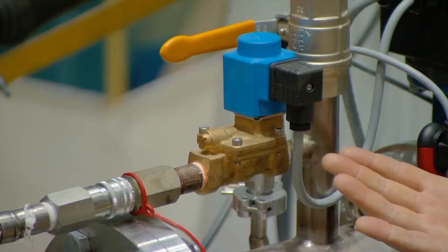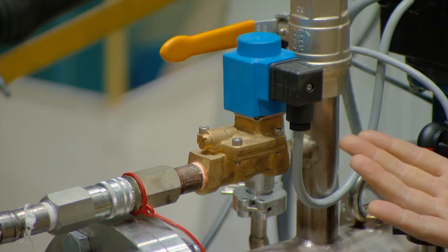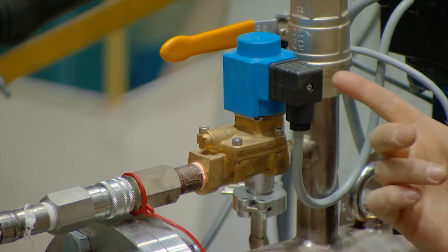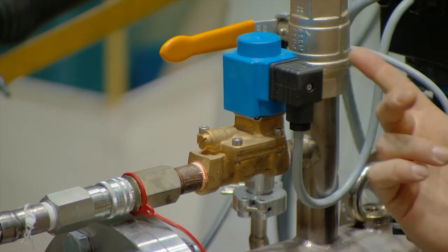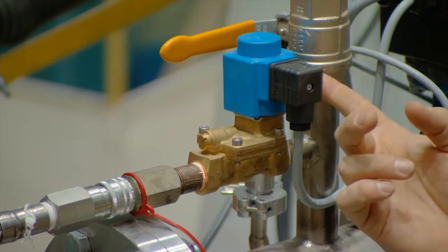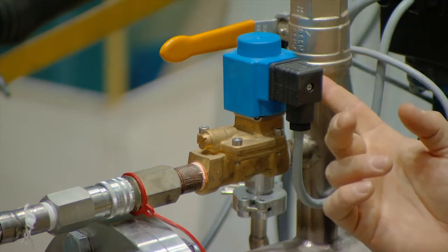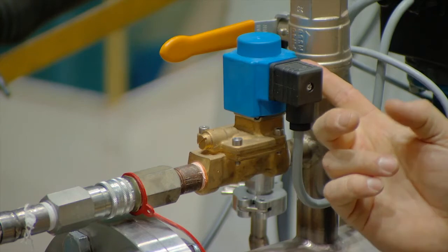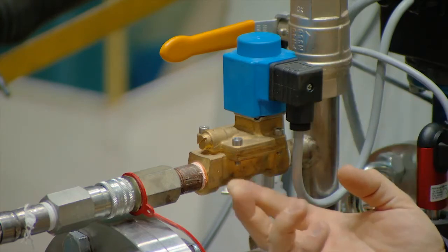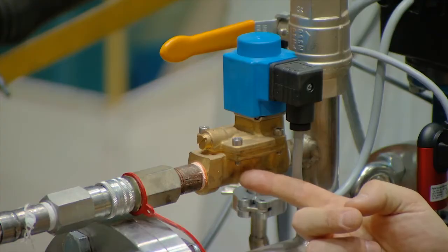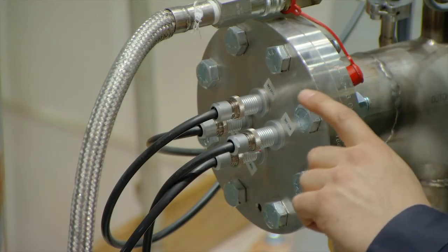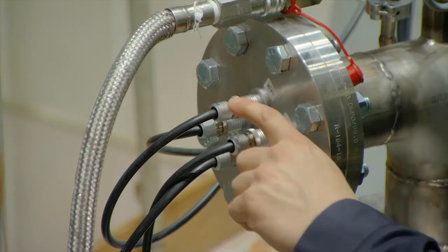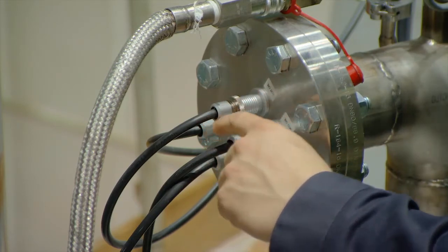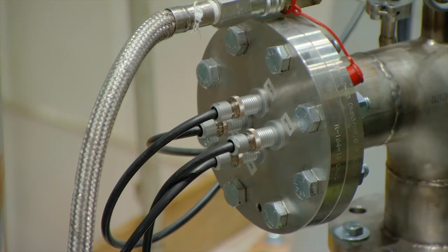Okay. This valve here is used to control the dry air being injected into the machine for the heating cycle. This is the control for it. It's an actual coil. Unlike the previous valve, when there is loss of power, this valve closes. This is the control for it, the coil. This is the actual valve right here, and here is your connection for your dry air. Okay, these are the 4 probes that are installed in the transformer, the thermocouples. There's 4 of them, 1, 2, 3, and 4. These are installed in the top and bottom of the transformer winding to see what temperature is actually inside the transformer during the heating of it.